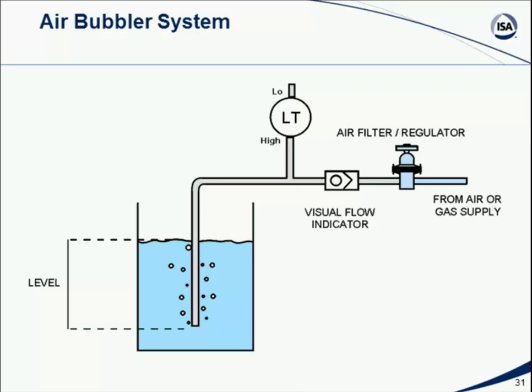In other words, fluid wants to enter the pipe and go up to the level that's in the tank. For me to blow that fluid down, out, and keep it out, I've got to blow air into that pipe and continue blowing air into that pipe, letting it escape out the bottom end. But the pressure into that pipe has to be at least as great as the pressure down at the bottom of the pipe. So in other words, at the bottom of this bubbler pipe, there's a liquid pressure based on the level, and the airflow in has to match that. And we can use that scheme.